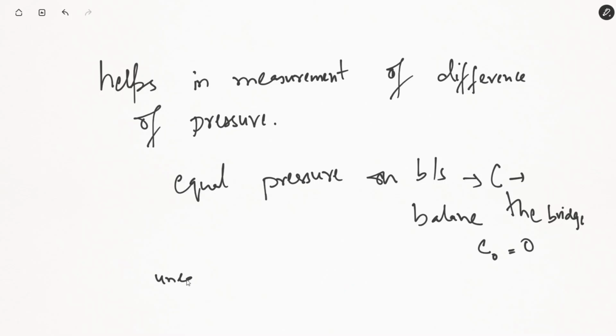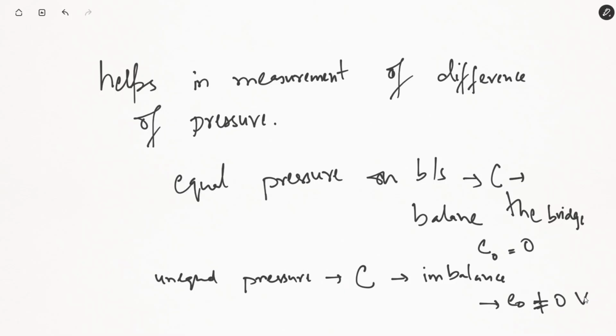Unequal pressure would result in a capacitance that will cause an imbalance. The bridge will no longer be balanced, meaning E naught will not be equal to 0 volts at that time. So you can actually say whether the system has equal pressure on both sides, or unequal pressure.